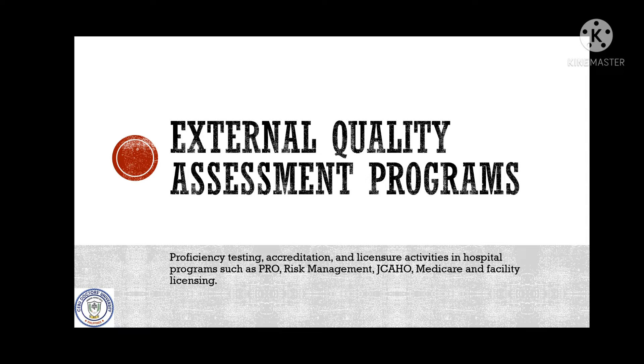This topic focuses on laboratory-based programs and other plans as part of the indicators of the overall quality performance of the institution. External quality assessment programs may be roughly divided into two types: one, proficiency surveys, in which blind specimens are sent by an external agency for analysis and comparison with other laboratories; and two, licensure and accreditation programs, which involve on-site inspections. The line between these two groups is often blurred because they are so closely intertwined, but the division provides a means for review.